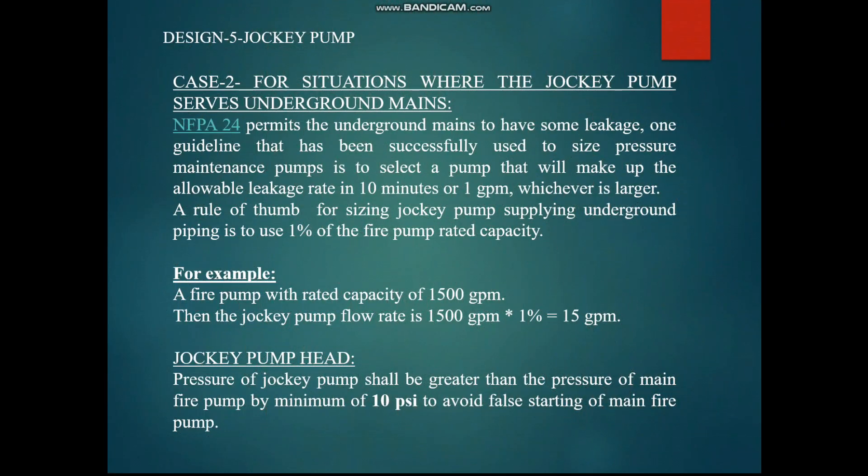For Case 2, where the fire pump is in a central yard supplying different buildings through underground pipelines: NFPA 24 permits underground mains to have some leakage. One guideline commonly used is to select a pump that makes up the allowable leakage rate in 10 minutes or 1 gpm — whichever is larger. As a rule of thumb, the jockey pump is sized at 1% of the main fire pump capacity. For example, with a 1500 gpm fire pump, the jockey pump would be 15 gpm.